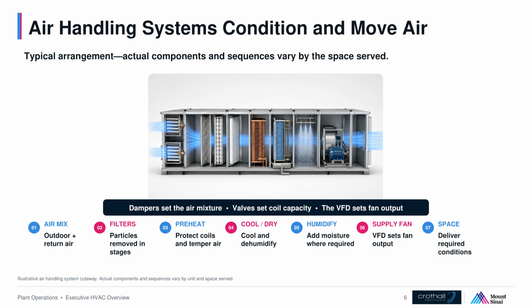A supply fan, usually controlled by a variable frequency drive, moves the treated air to the space. Dampers set the mixture, valves set coil capacity, and sensors tell the sequence what happened. Some systems use 100% outdoor air, higher filtration, or dedicated exhaust, depending on the space. At the zone, a variable air volume box reads temperature, modulates its damper, holds the permitted ventilation minimum, and reheats when needed. But comfort is not always the governing rule.